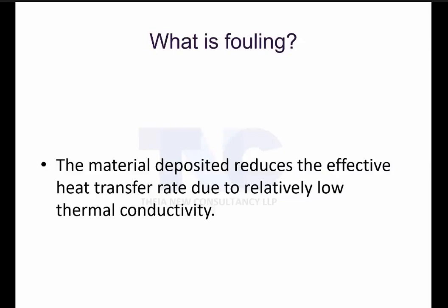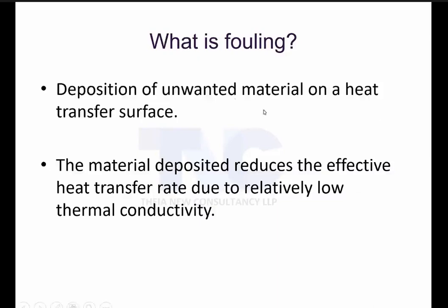So what happens when fouling is happening? Those deposits reduce the effective heat transfer rate across the heat exchanger, and the heat exchanger duty will come down. This is the deposition of unwanted materials on the heat transfer surface, in your tubes or in your shells. Those deposits have very low thermal conductivity, so your heat transfer will come down, and exchanger performance will go down eventually.